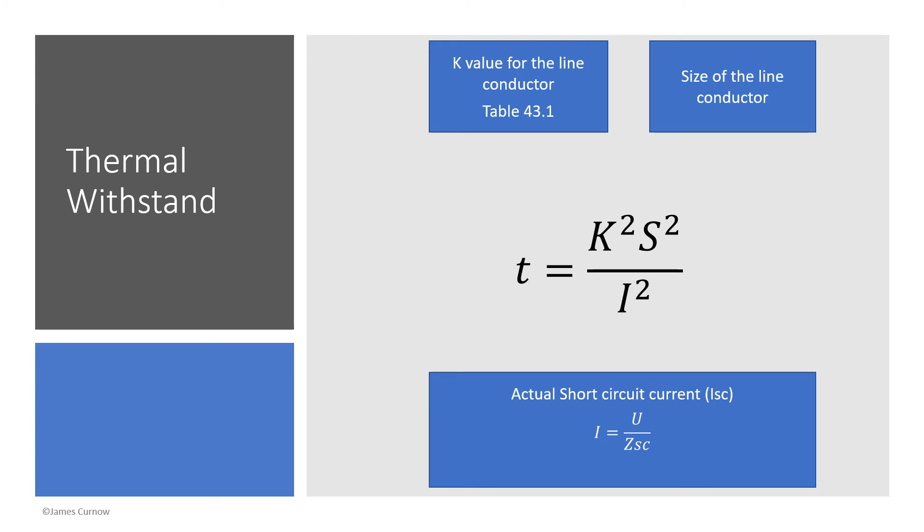S is the size of the line conductor and I is the actual short circuit current which we find by dividing the voltage by the Zsc. Now Zsc is the loop between line and neutral so you may have also seen this as Z brackets L to N on your test kit.